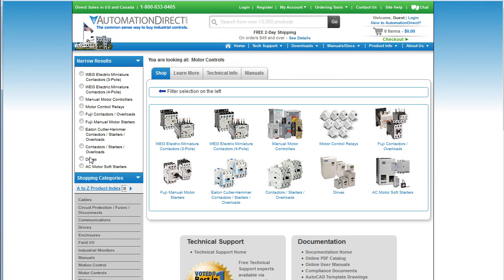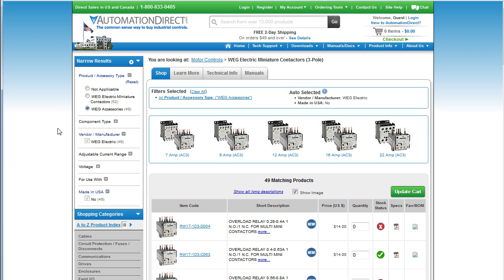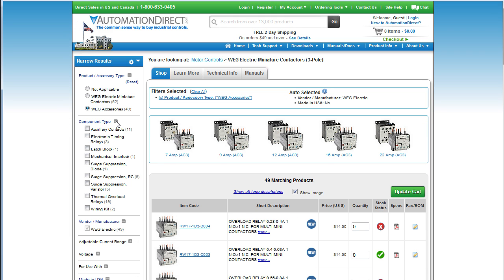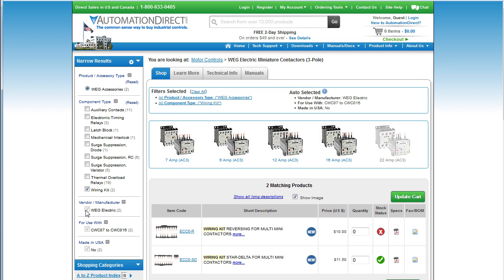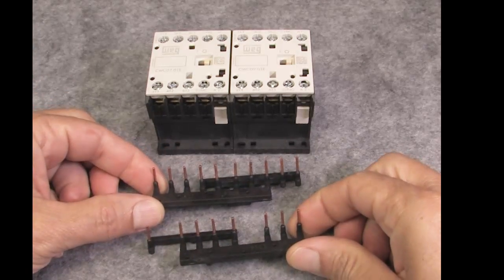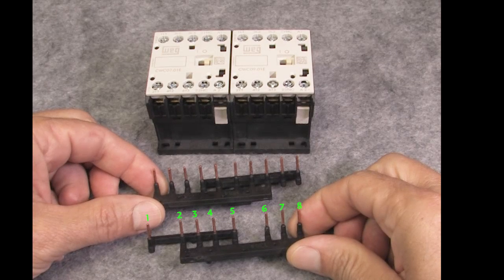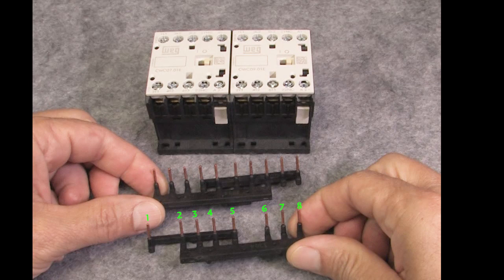The WEG mini contactors on the other hand have a really slick way of doing all of this in one fell swoop. Look under Motor Control, WEG mini contactors, WEG accessories, component type, wiring kit. Look, there is only one part number. The reason for this is the reversing kit works for all 3 pole WEG mini contactor sizes with or without an overload. Why are there so many posts on this module? Shouldn't there just be 3 for one contactor and 3 for the other like we have with the Fuji part? This one has 8 leads and this one has 10. What's that all about?